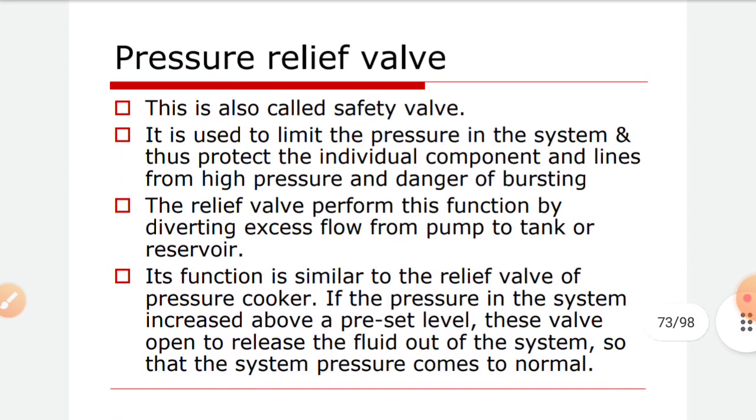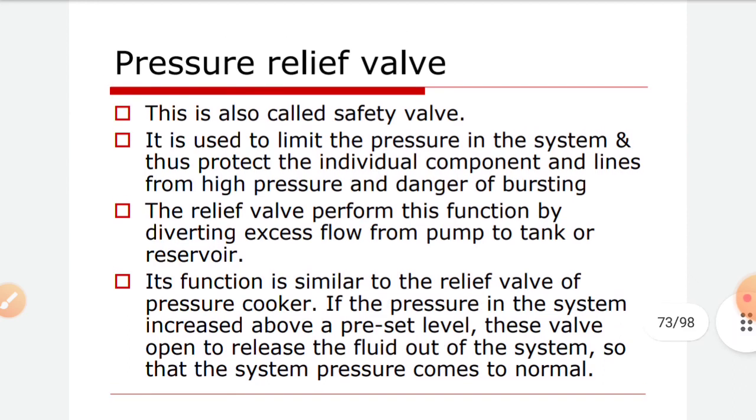So the first one is a pressure relief valve. The pressure relief valve is also called a safety valve. It is used to limit the pressure in the system and thus protect the individual components and lines from higher pressure and danger of bursting. The relief valve performs this function by diverting excess flow from the pump to the tank or reservoir.